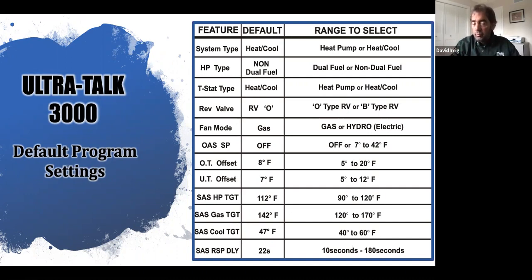These are temperatures that my supply air sensor is looking to achieve to satisfy a heat call or cooling call. I want to see that call. Once I'm there, I stop the equipment from the process of either staging up or staging down. If I achieve that particular target temp, that's the temp that I'm comfortable with that will take care of that call in a timely manner.